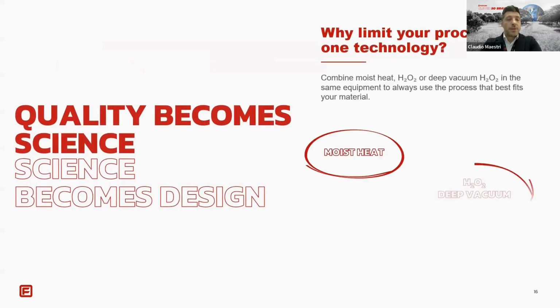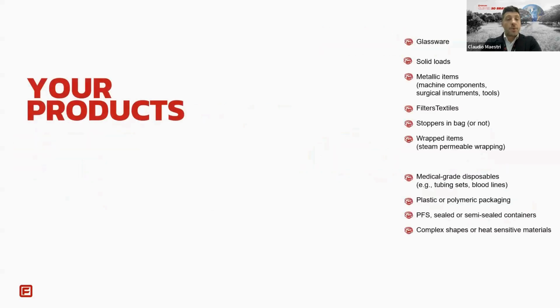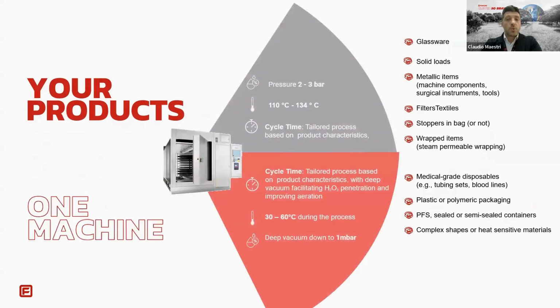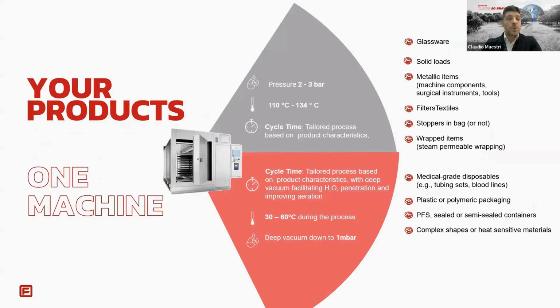So the question is, why limit your process to one technology? As Fedegari, we combine two technologies in one equipment, meaning moist heat and H2O2 deep vacuum in one only equipment. One machine suitable to treat and sterilize the widest range of products and packages. As we can see, with moist heat we can sterilize glassware, solid loads, metallic items, filters, textiles, stoppers in bag or not, wrapped items, and then all the items and materials that we already saw with H2O2 deep vacuum, like medical grade disposables, plastic or polymeric packaging, prefilled syringes, complex shapes, or heat sensitive materials.